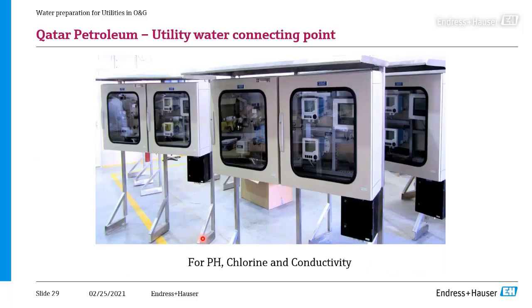And this is the last example. These panels are installed at Qatar Petroleum at the utility water connecting point. There is a local utility provider who supplies the makeup water to this client, Qatar Petroleum, and to measure that the makeup water meets the criteria and quality, they have these measuring stations in place to measure pH, chlorine, and conductivity, so they are sure the water comes in good quality from this provider and can be used without any doubts in their process. Therefore, they use these panels.